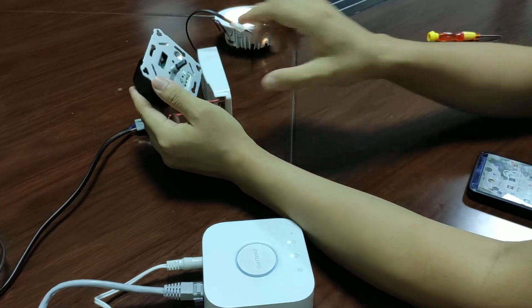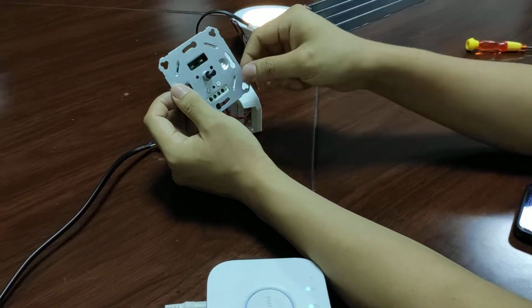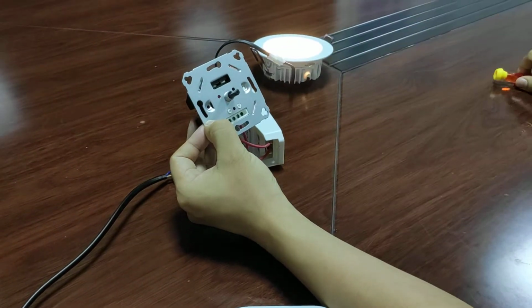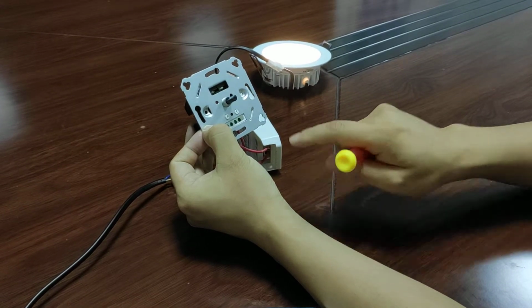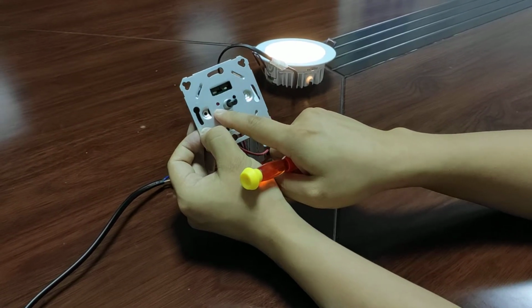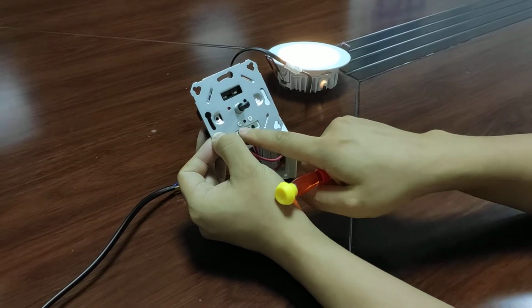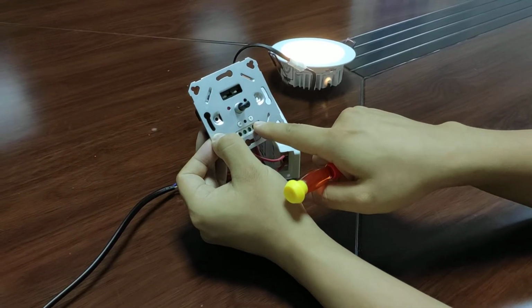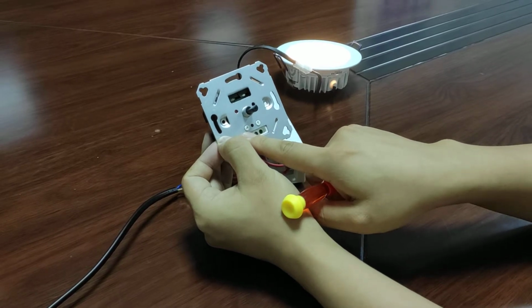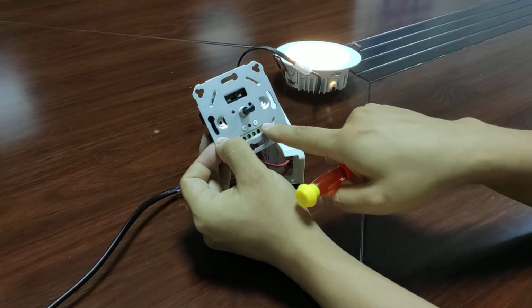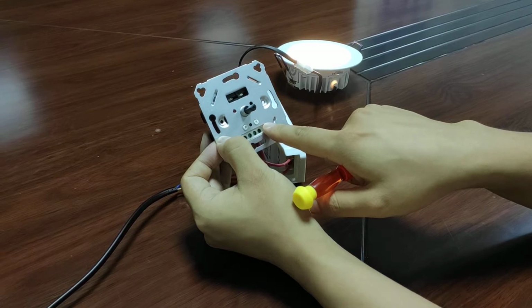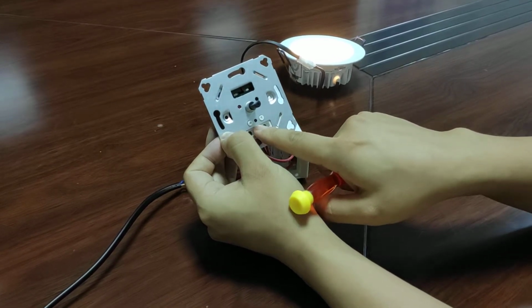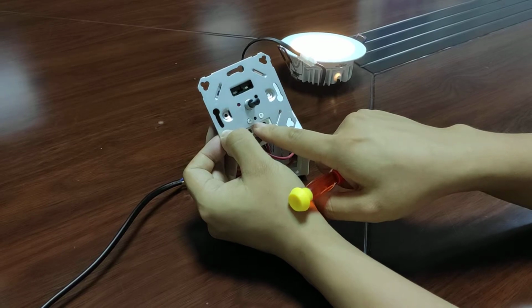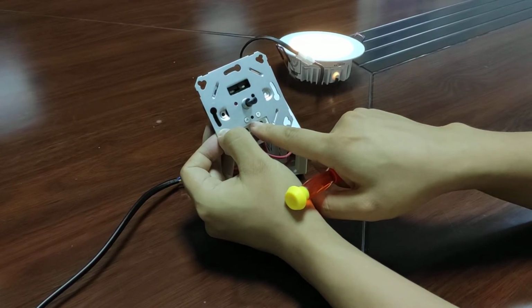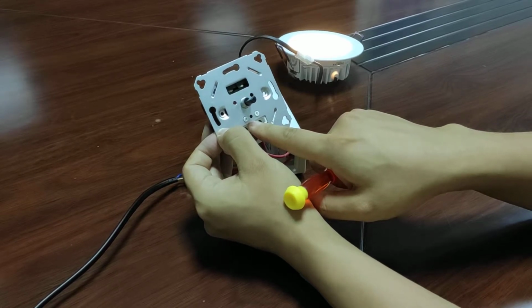Firstly, let us do a brief introduction of our European standard Zigbee dimmer. You will see on the plate there is a red indicator, and there are two micro adjustment switches, of which the left is for the minimum brightness adjustment, and the right is for the maximum brightness adjustment. And in the middle, there is a resetting button, which allows you to reset the dimmer to the factory setting so you can connect with any other gateway.